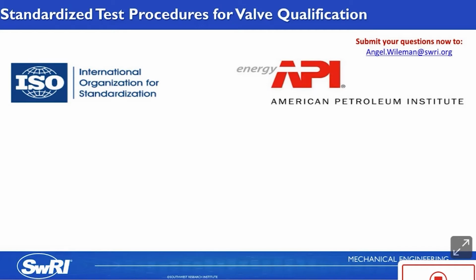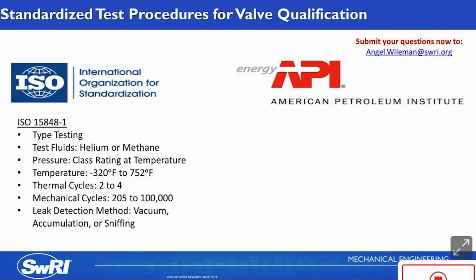The most common standardized procedures for fugitive emissions testing are ISO 15848-1 and -2 and API 624 and 641. And there are also some specific publications by end users with their own criteria, but they're generally pretty similar to these, maybe a bit more restrictive. So starting with ISO 15848-1, this is a standard for measurement, test, and qualification procedures for fugitive emissions. And the -1 denotes that it is for type testing of valves.